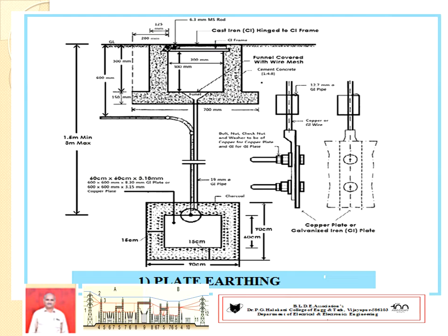Then the top cover, it consists of some metal cover opening with funnel arrangement at the bottom. Then through the GI pipe, it is connected to the electrode. Normally we can use copper as electrode, and it has the best conductivity, low resistivity also. Only drawback is higher cost. Hence, due to cost, copper plate is limited. In place of copper plate, generally we are using GI plate and cast iron plate. GI plate is more commercially used as shown in figure.